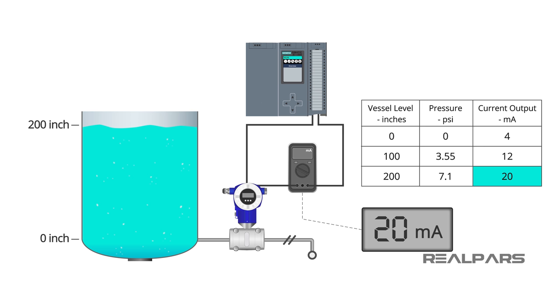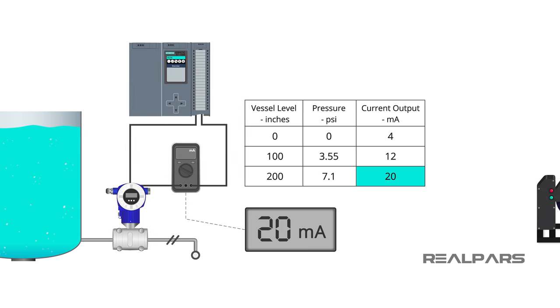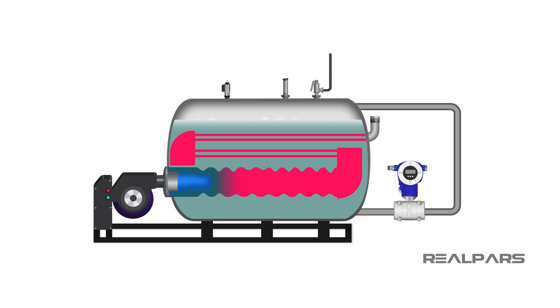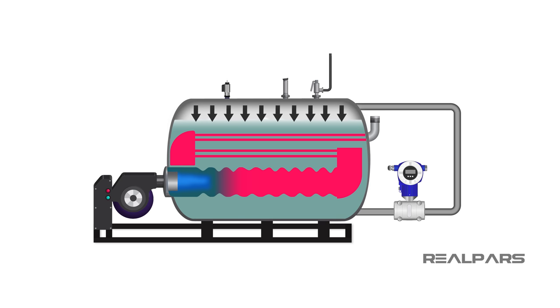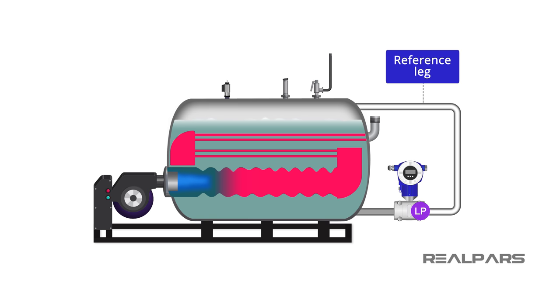So far, we have only considered open vessels. Let's move on to the level measurement of closed vessels. The major difference between open and closed vessel level measurement is the fact that we need to consider the pressure in the vapor above the liquid in the closed vessel. This vapor pressure exerts a force on the surface of the liquid. We can compensate for the vapor pressure by connecting the low pressure side of the differential pressure transmitter to the top of the vessel through a pipe referred to as a reference leg.